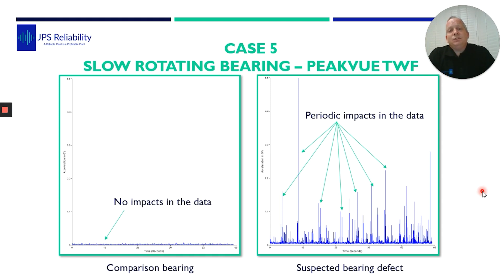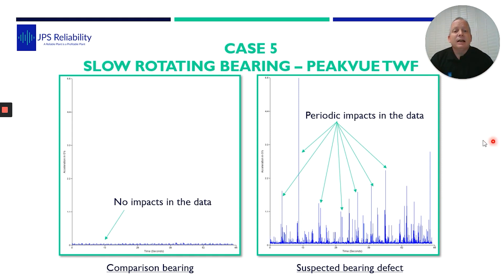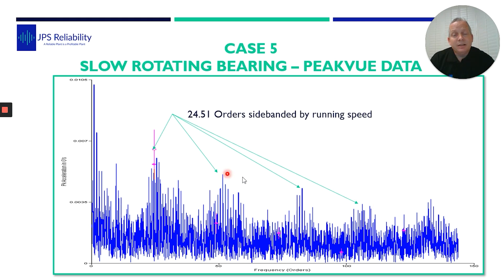On our first data collection we chose PeakVue, using the time waveform, sampling really high. We played with different types of filters and bandpass filters, deciding on one that gave us the best data. Comparing one slurry pot bearing to another, you could straight away imagine one going 'ting ting ting' — something wasn't right. Running the FFT on that waveform, even though levels were at 0.0105, we could see a peak at 24.51 orders sidebanded by rotational speed — that is the inner race defect frequency for this bearing.